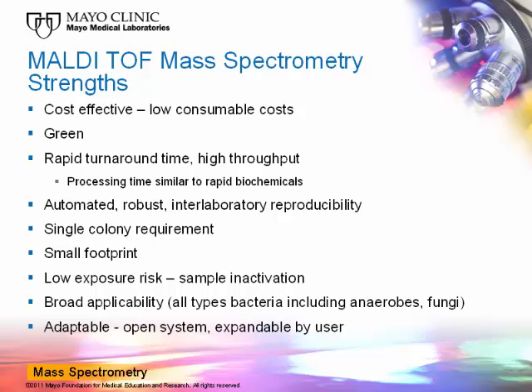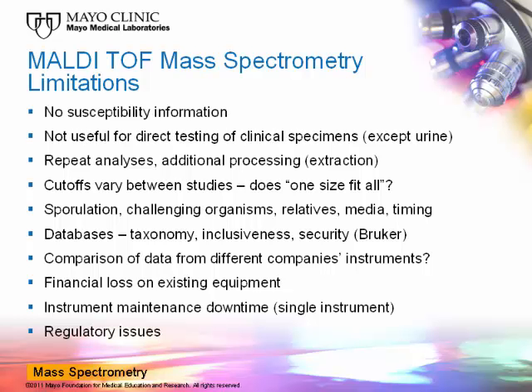There are limitations to MALDI-TOF mass spectrometry. No susceptibility information is provided, and the technology is not generally useful for testing clinical specimens directly. Some organisms require repeat analyses and additional processing. The acceptable score cutoffs vary between studies, and some closely related organisms are not differentiated. Sporulation may challenge identification. The available databases could use improvement, and comparison of data from different companies' instruments is not feasible. Laboratories acquiring the needed equipment will suffer financial loss on existing equipment.